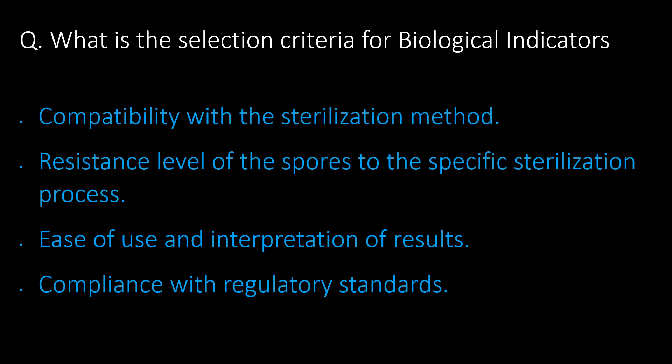What is the selection criteria for biological indicators? Four points are considered when selecting biological indicators in the pharmaceutical industry: first, compatibility with the sterilization method; second, resistance level of the spores to the specific sterilization process; third, ease of use and interpretation of results; fourth, compliance with regulatory standards.